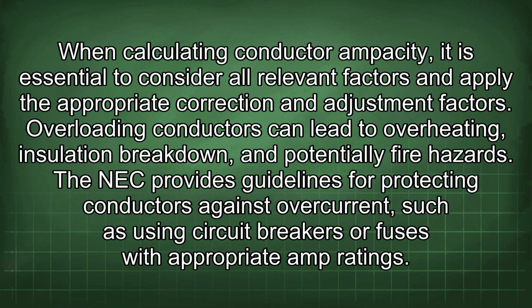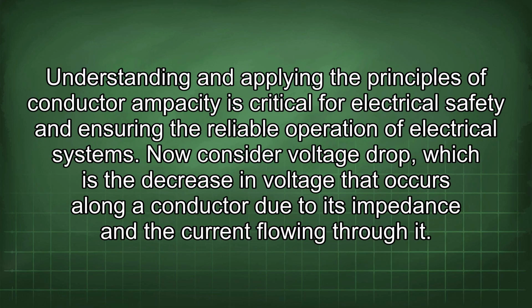When calculating conductor ampacity, it is essential to consider all relevant factors and apply the appropriate correction and adjustment factors. Overloading conductors can lead to overheating, insulation breakdown, and potentially fire hazards. The NEC provides guidelines for protecting conductors against overcurrent, such as using circuit breakers or fuses with appropriate amp ratings. Understanding and applying the principles of conductor ampacity is critical for electrical safety and ensuring the reliable operation of electrical systems.